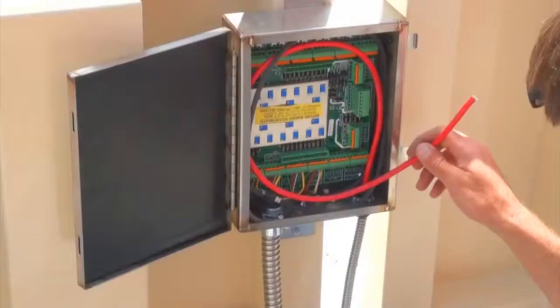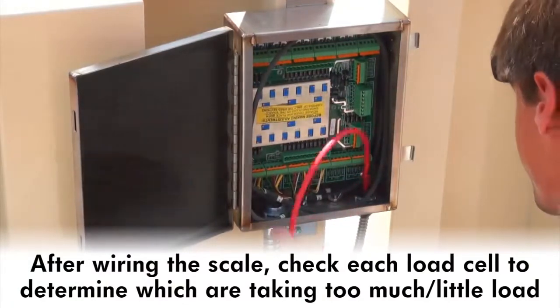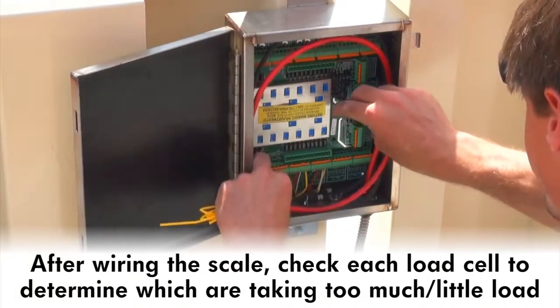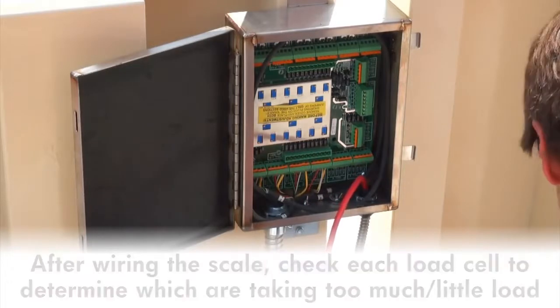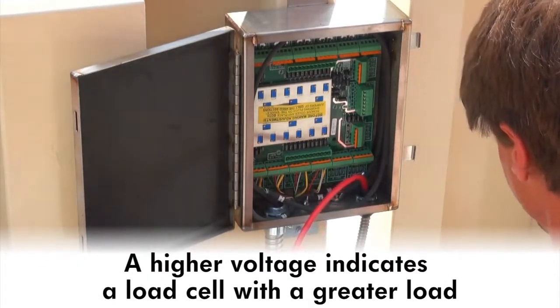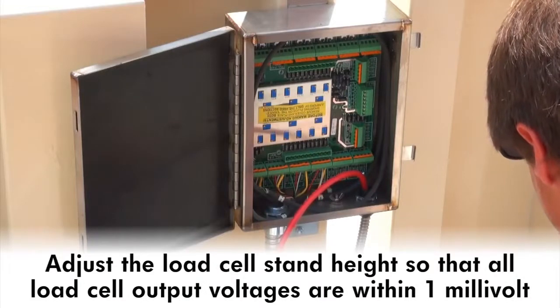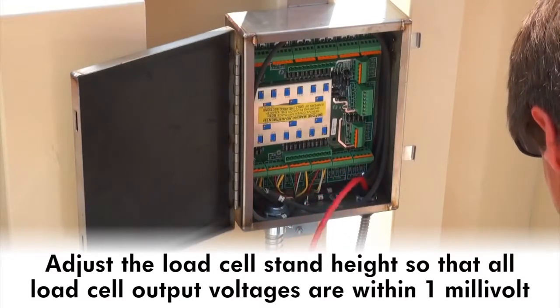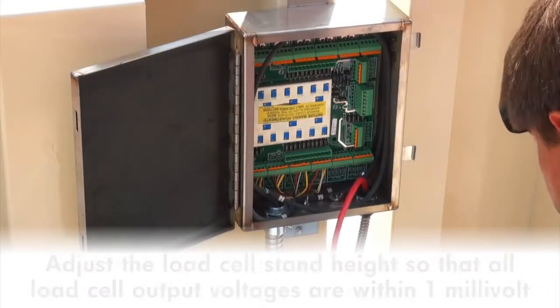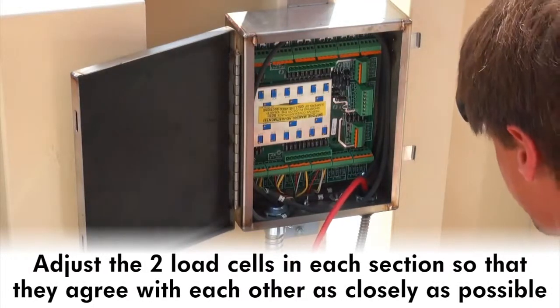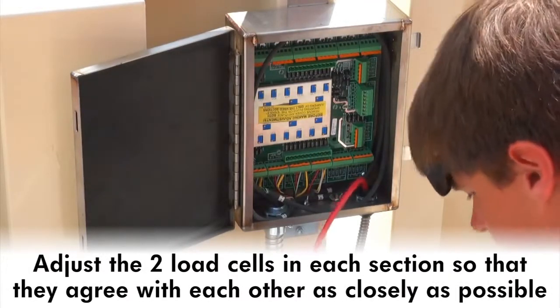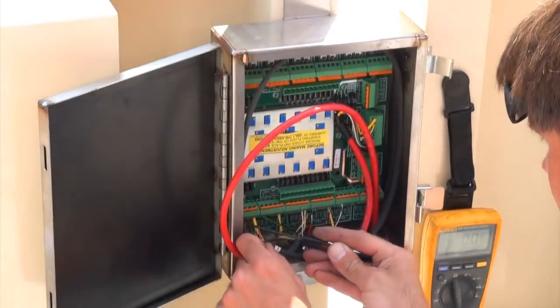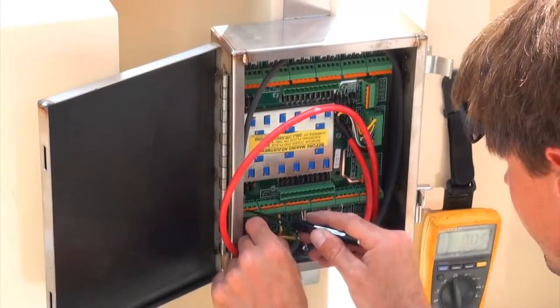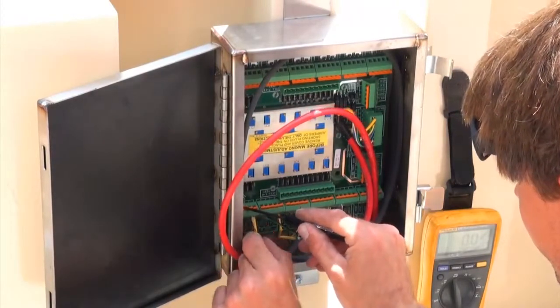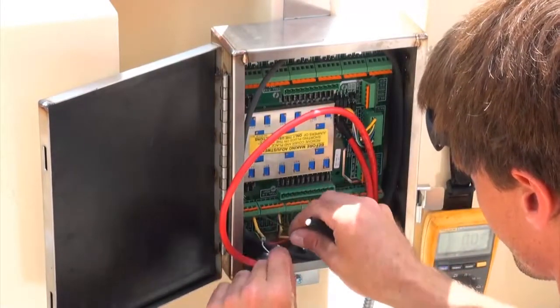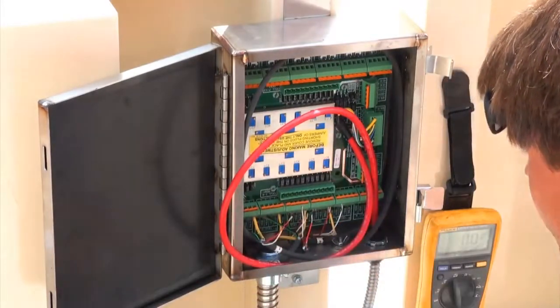After wiring the scale to a power source, check each load cell to determine which cells might be taking too much or too little load. A higher voltage indicates a load cell with a greater load. Adjust the load cell stand height so that all load cell output voltages are within 1 millivolt or less of each other. Adjust the two load cells for each section so that they agree with each other as closely as possible. A little extra effort at this point is time well spent since it has direct bearing on the ease and accuracy of section sealing the scale, as well as the customer satisfaction from the long-term operation of the scale.